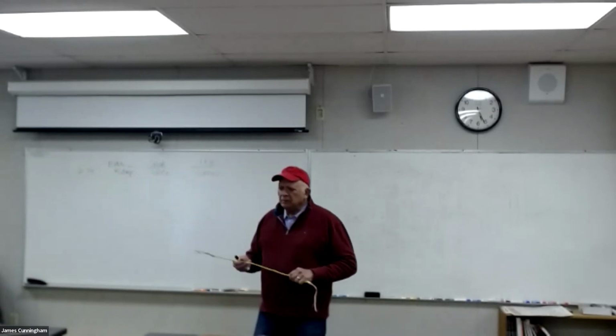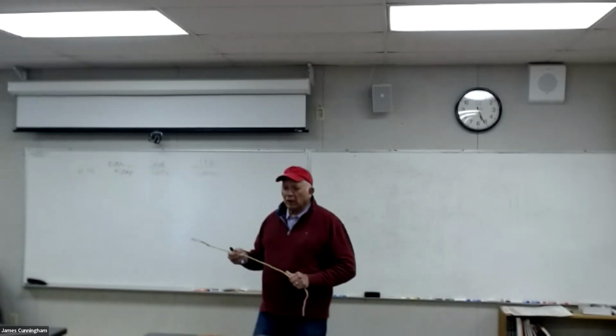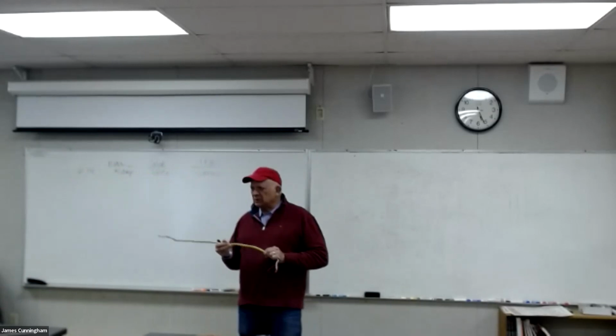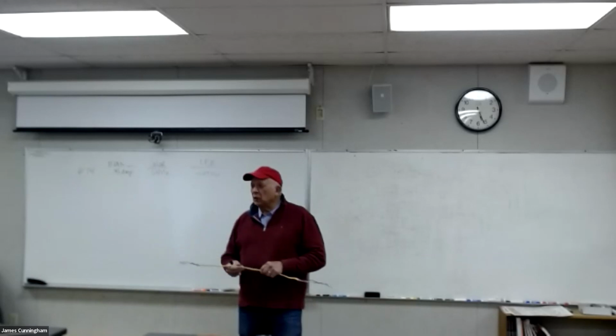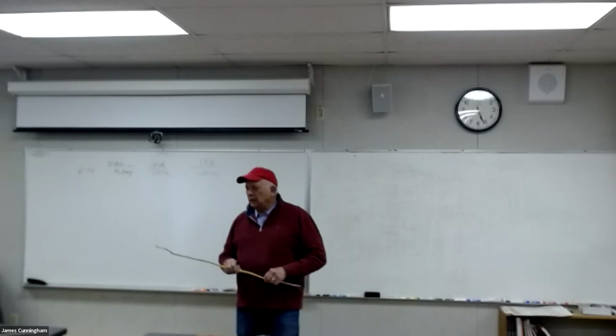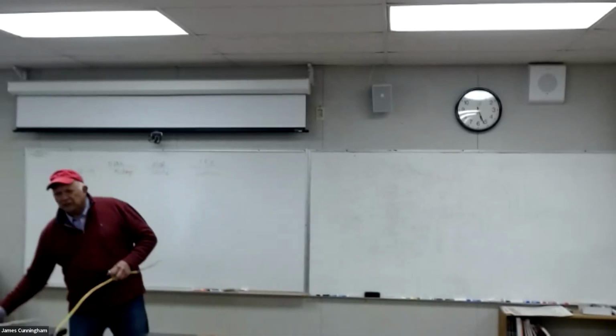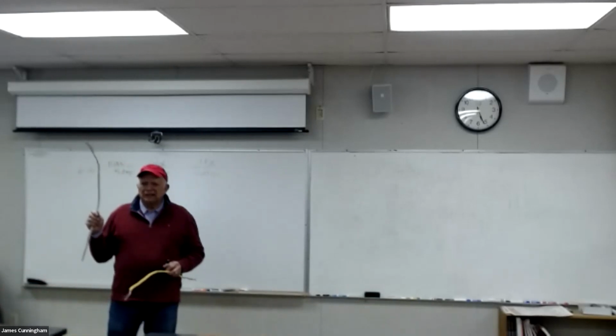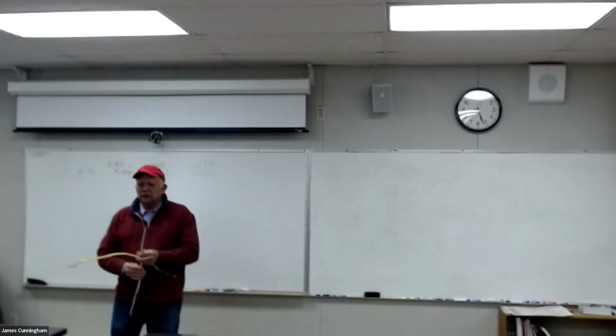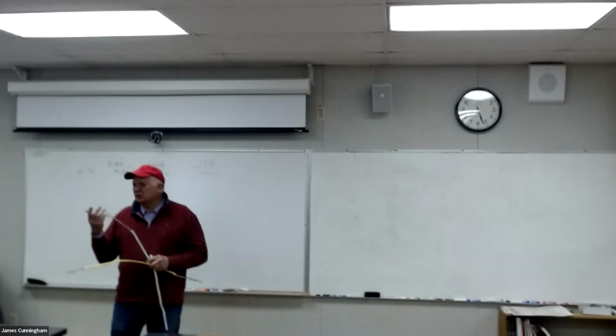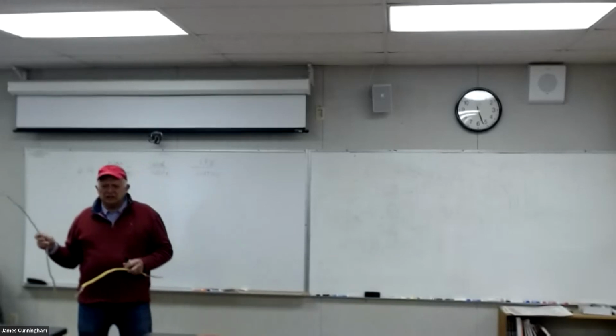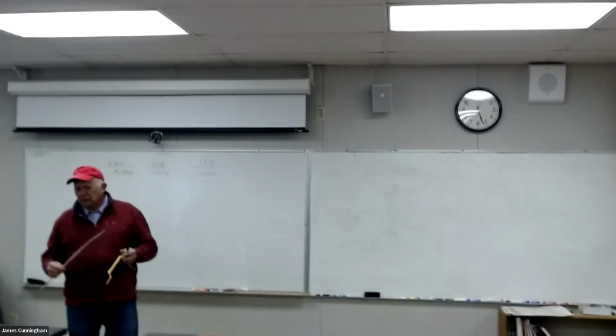It's been a while, and also it used to be that they didn't have a color code for the wire. So now it makes it really easy when the inspector comes, he can take a look, and if he sees a plug with white wire going to it, he'll know that that's not the code. He'll make you rewire it. Back in the 70s and 80s, a lot of the Romex was either black or white. So you might have circuits that were number 12 wire. So don't make the mistake, if you're working on an older house and you see a white wire, don't assume that it's a number 14. It could be that it's a number 12. So you have to actually look at it and see. But in new work, it's been at least 10 years that the 14 has to be used for lighting, just lighting.